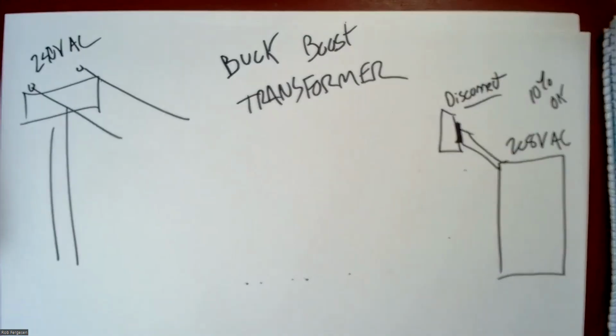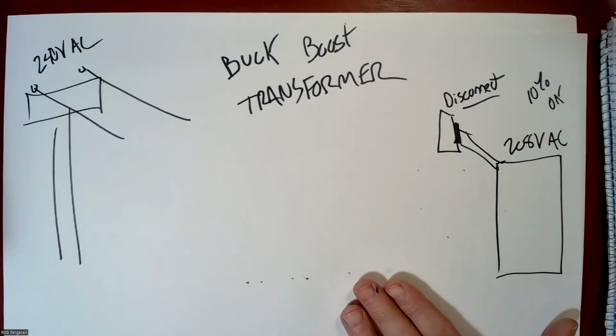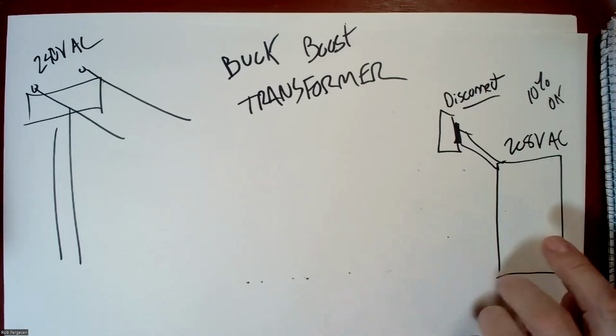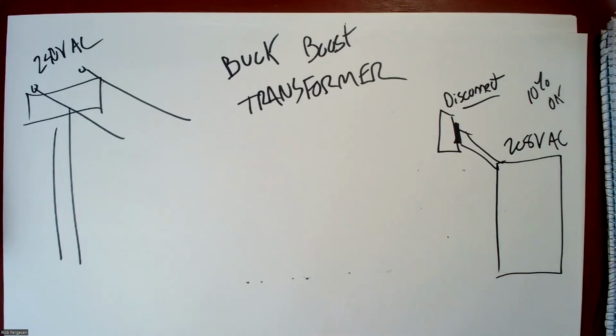The example we're going to use is a simple transformer for decreasing my voltage. The same exact transformer can also be used to increase voltage depending on how you wire it. So what we're going to do, number one, is we're going to go through the process of selecting a transformer, and then we're going to look at the wiring diagram in a transformer, typically for this application.